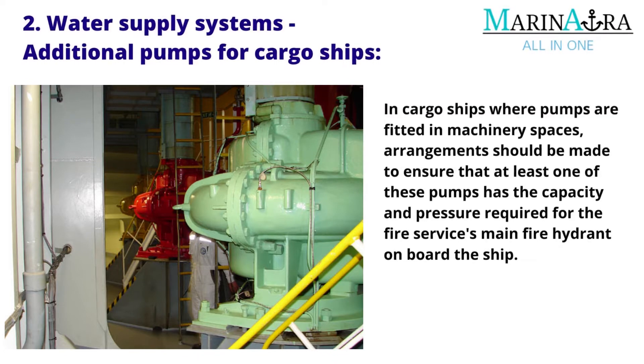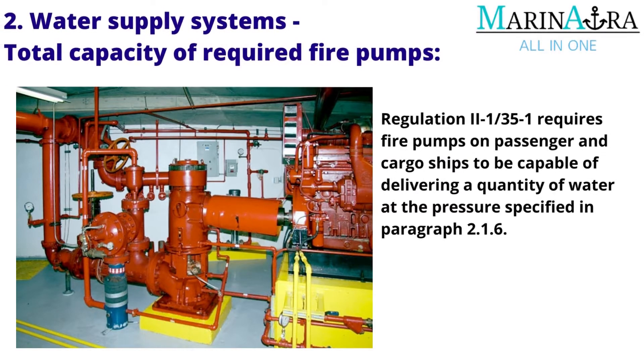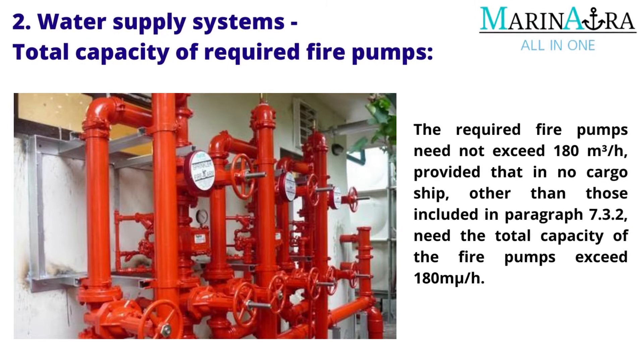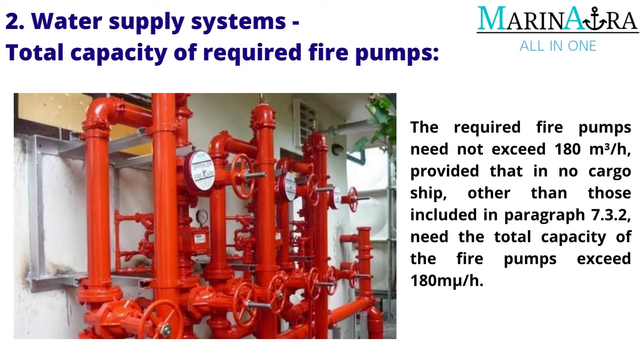In cargo ships where pumps are fitted in machinery spaces, arrangements should be made to ensure that at least one of these pumps has the capacity and pressure required for the fire main on board the ship. Total capacity of required fire pumps: Regulation II-1/35-1 requires fire pumps on passenger and cargo ships to be capable of delivering a quantity of water at the specified pressure. The required fire pumps need not exceed 180 m³/h, provided that in no cargo ship other than those included in paragraph 7.3.2 need the total capacity of the fire pumps exceed 180 m³/h.